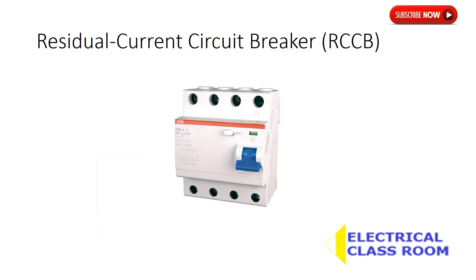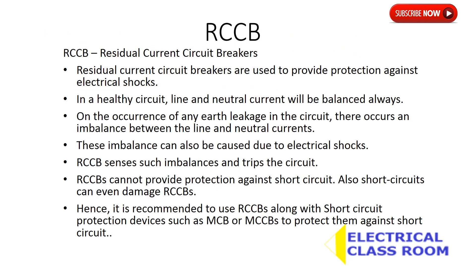Residual current circuit breakers are used to provide protection against electrical shocks. In a healthy circuit, line and neutral current will be balanced always. On the occurrence of any earth leakage in the circuit, there occurs an imbalance between the line and neutral currents. This imbalance can also be caused due to electrical shocks. Residual current circuit breakers sense such imbalances and trip the circuit.